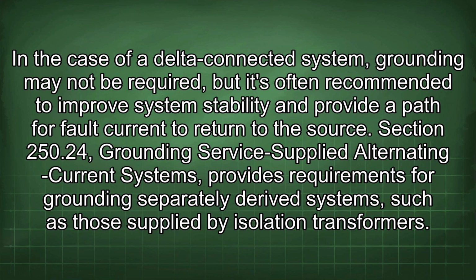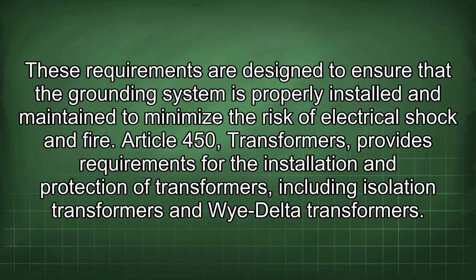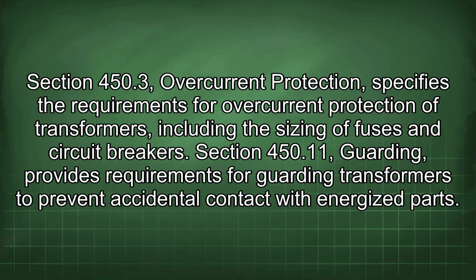250.24 Grounding Service-Supplied Alternating Current Systems provides requirements for grounding separately derived systems, such as those supplied by isolation transformers. These requirements are designed to ensure that the grounding system is properly installed and maintained to minimize the risk of electrical shock and fire. Article 450 Transformers provides requirements for the installation and protection of transformers, including isolation transformers and wye-delta transformers. Section 450.3 Overcurrent Protection specifies the requirements for overcurrent protection of transformers, including the sizing of fuses and circuit breakers. Section 450.11 Guarding provides requirements for guarding transformers to prevent accidental contact with energized parts.